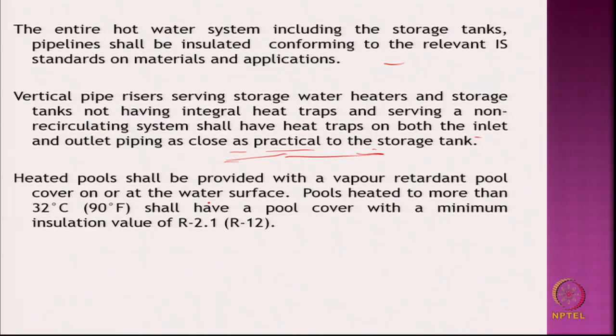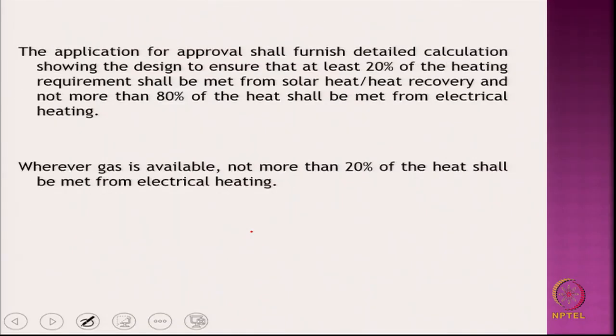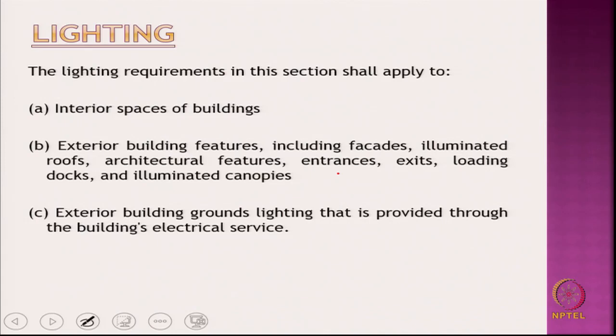So, minimizing the loss, pools heated to more than 32 degrees centigrade shall have a pool cover with a minimum insulation of this. So, these are the mandatory requirements given. Application for approval shall furnish all these details. Wherever gas is available, not more than 20% of the heat shall be met with electrical heating. So, if gas is available, use 80% gas and 20% electrical.